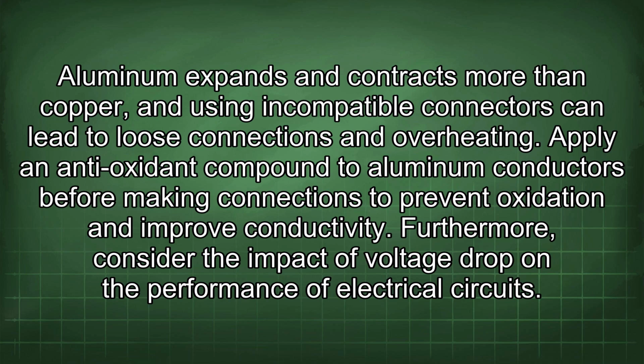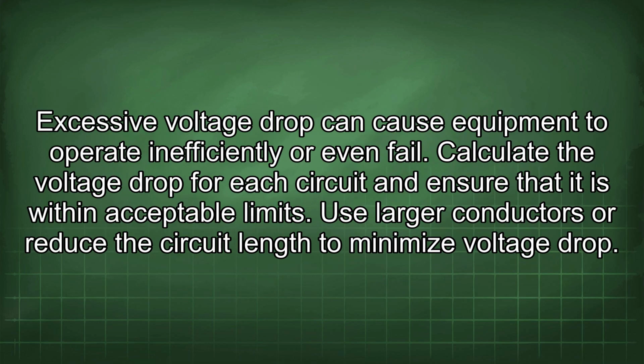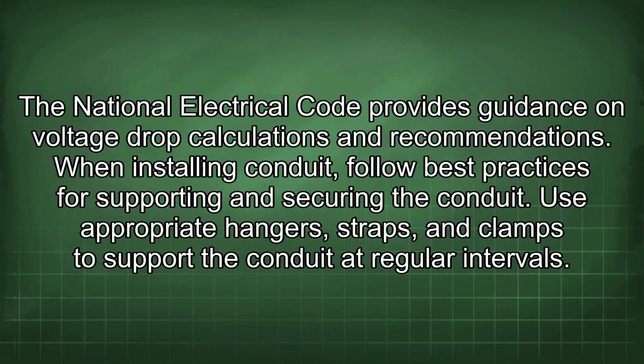Furthermore, consider the impact of voltage drop on the performance of electrical circuits. Excessive voltage drop can cause equipment to operate inefficiently or even fail. Calculate the voltage drop for each circuit and ensure that it is within acceptable limits. Use larger conductors or reduce the circuit length to minimize voltage drop. The National Electrical Code provides guidance on voltage drop calculations and recommendations.